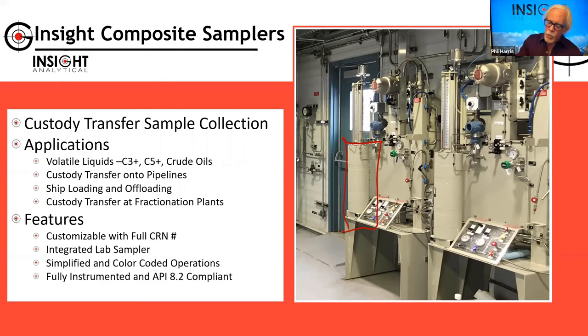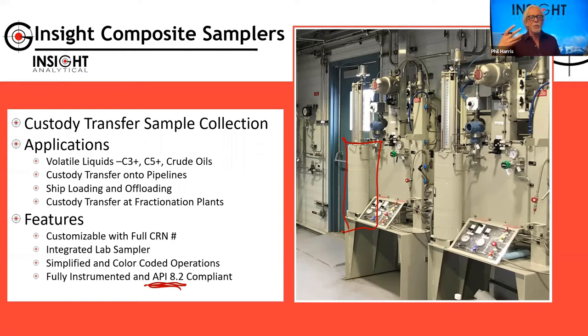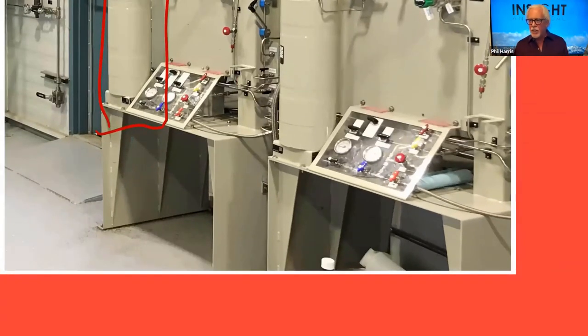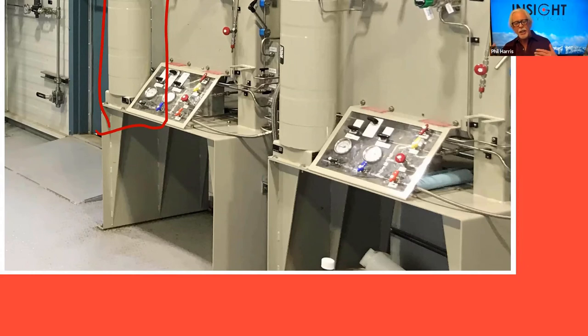We've done a fair number of unique things, and we're very cognizant of the American Petroleum Institute's API 8.2, which describes how to do this correctly. We wanted to make sure we did it right and made it really easy to operate. One thing we do with a lot of our sample systems is use color-coded valves, like you see there, so that when we write an operational procedure, it's easier for operators to say 'I'm supposed to turn the round red valve.' We try to consider this from a field operator's perspective.